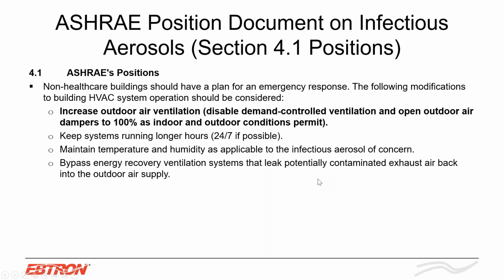And this is ASHRAE's position for non-healthcare buildings. We're just going to hit on non-healthcare. For healthcare buildings, they want you to increase the air change rates, and we can talk about that if we have any questions afterwards. But let's just look at non-healthcare buildings. Basically, non-healthcare buildings should have an emergency response. And what do they want you to do? They want you to try to increase your outdoor air ventilation to 100% as indoor and outdoor conditions permit, and disable any type of DCV, right? And as a design engineer, this is difficult to do, especially with existing systems, because a lot of times your systems were not designed to carry this type of load. And that's why ASHRAE says, as conditions permit. They want you to do the best that you can. But they also say they want you to maintain temperature and humidity as applicable to the infectious aerosol of concern. That's where EBTRON can also help you out.